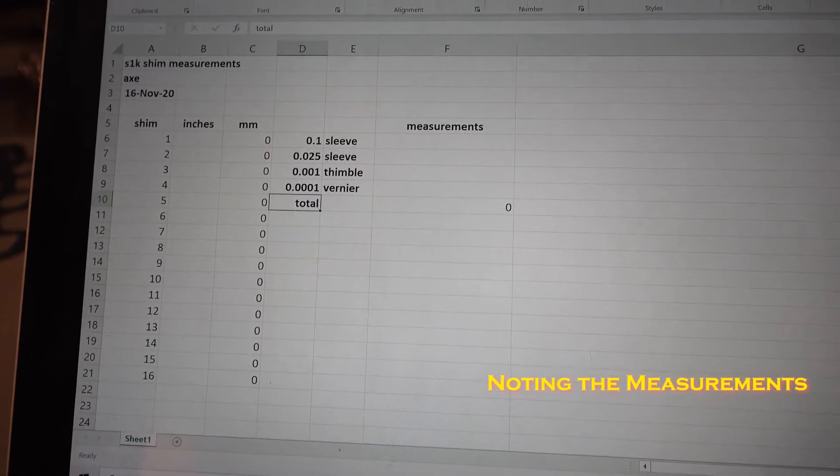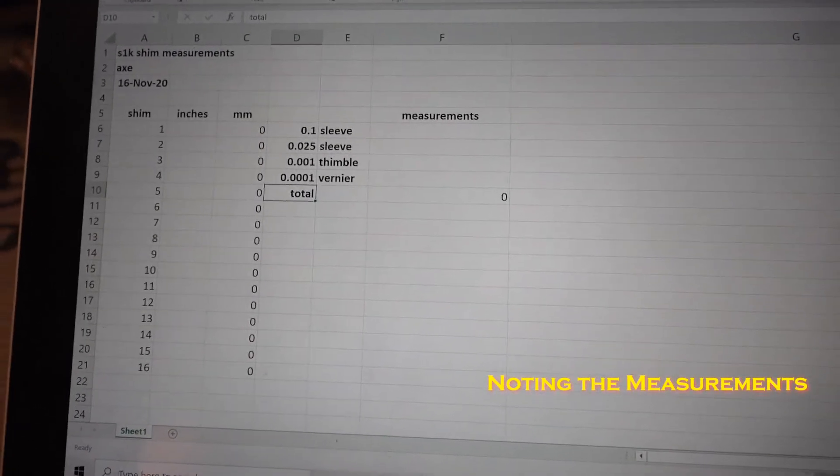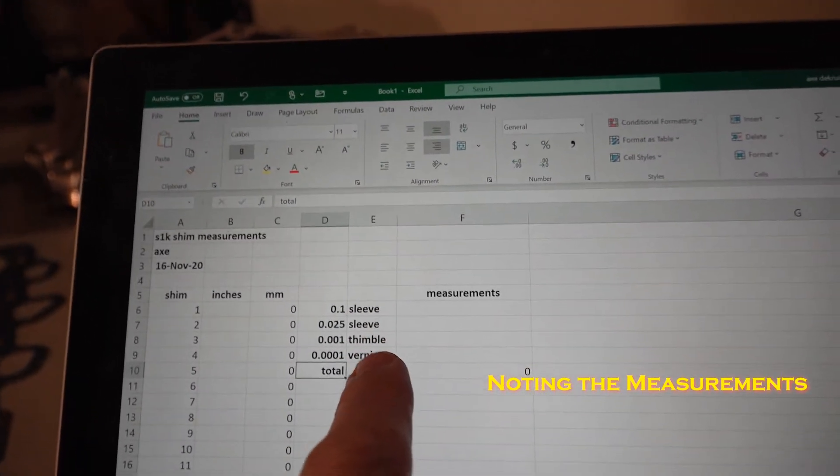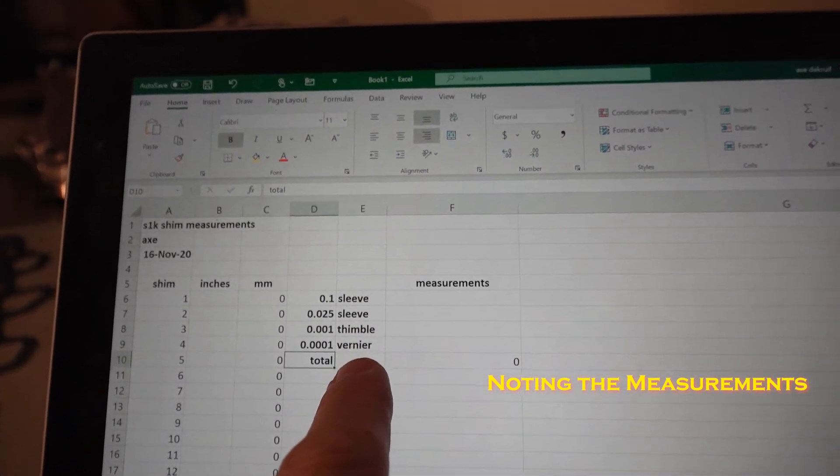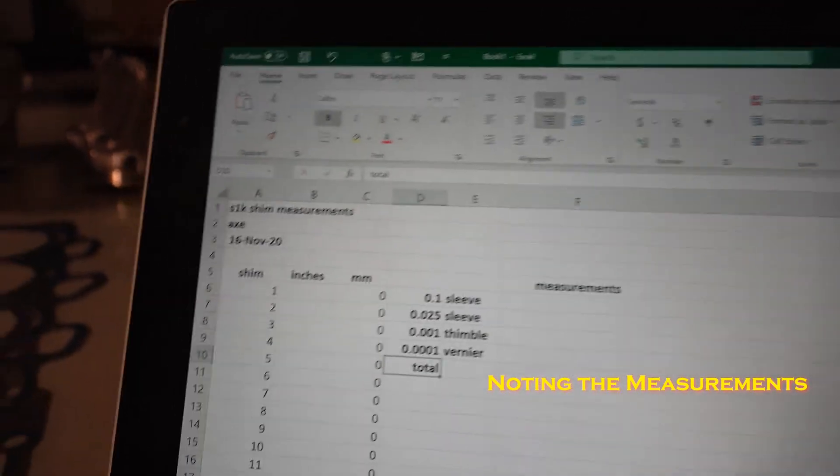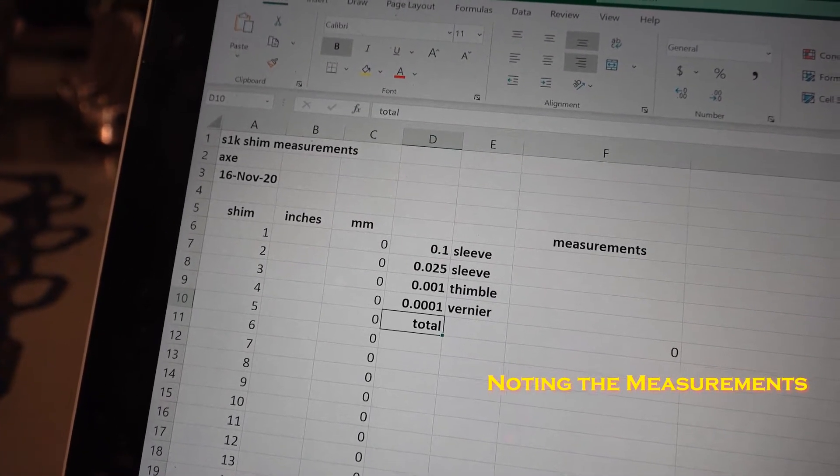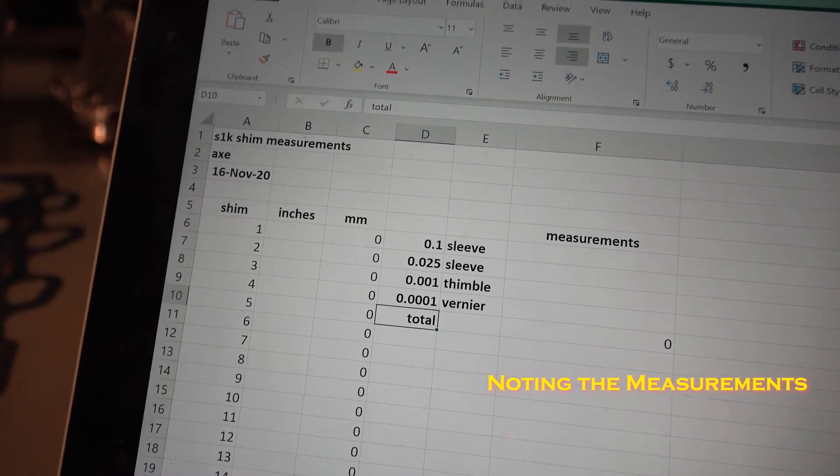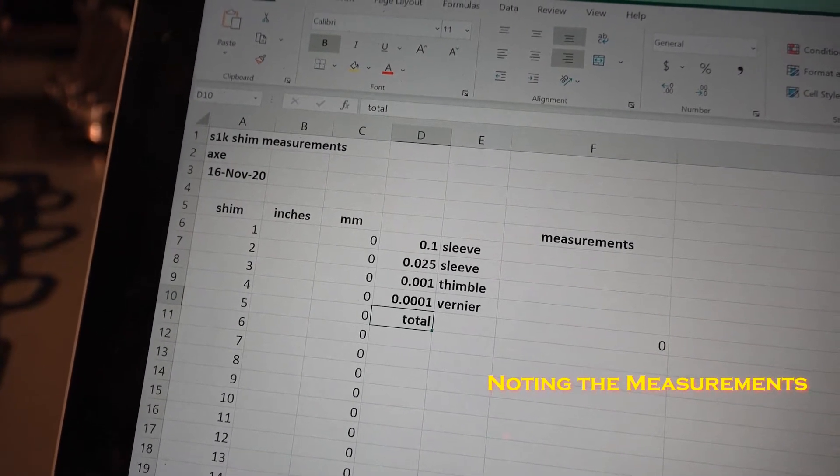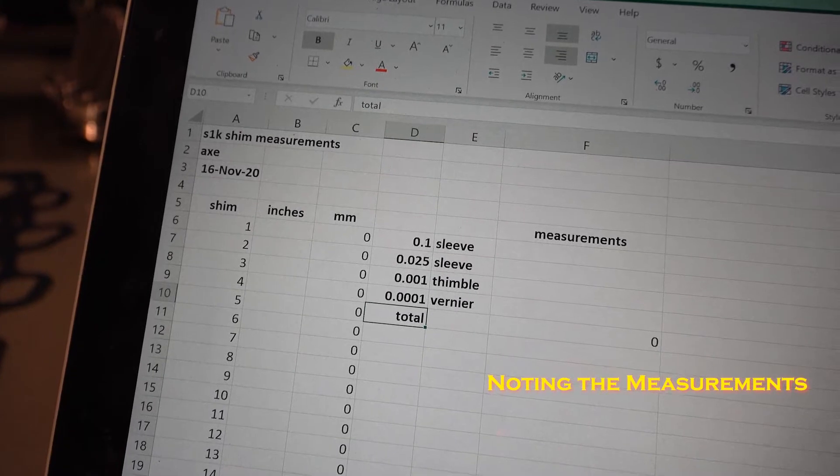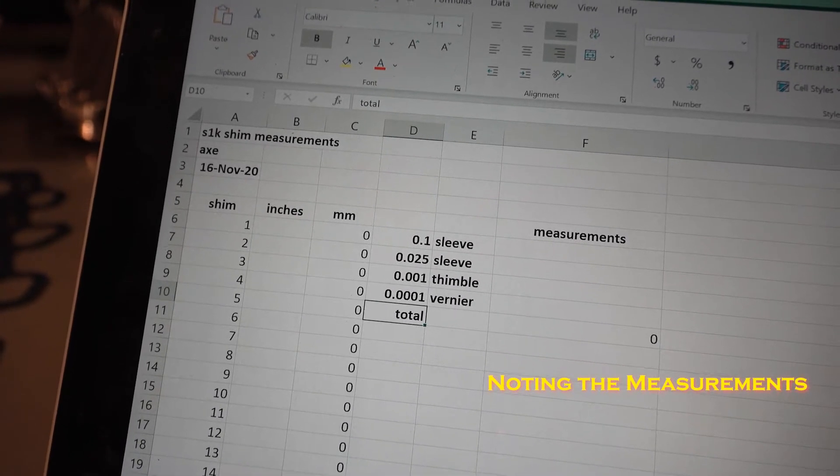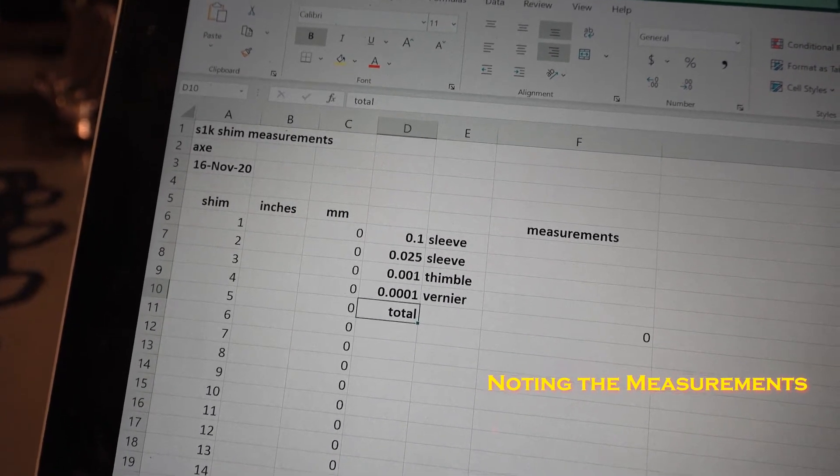Whether it's on a piece of paper or an Excel file like I've done, you want to set it up so that you have the measurements for your two sleeve measurements, one thimble measurement, and one vernier measurement. I've noted them as the sleeve being 100 thousandths measurement, then in increments of 25 thousandths, then 1 thousandth, then 1 ten thousandth.